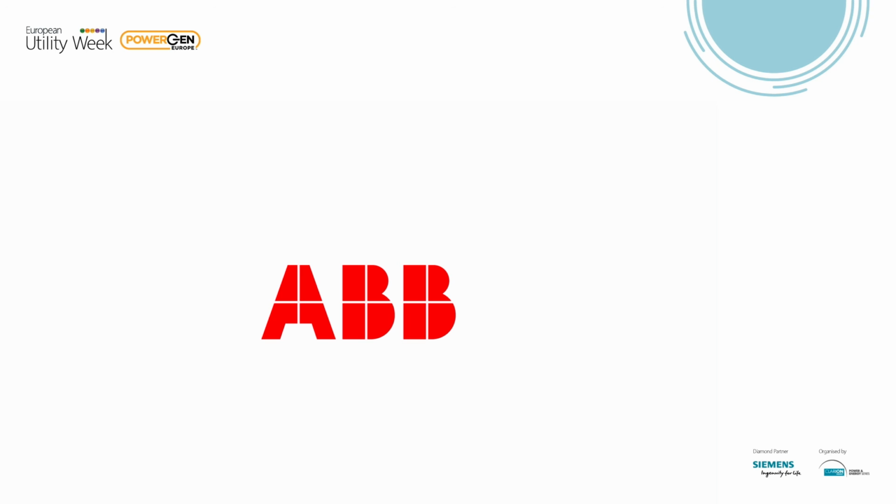We also need something called fast frequency response. The Irish grid did a very clever thing. They divided that into an inertia, which is unfortunately not very defined in time frame, which they call synchronous inertia response, and then they have fast frequency response, which comes afterwards. So you need the synchronous inertia response to help you reduce the rate of change of frequency, and to help you at the nadir, so that you avoid the frequency coming down too low. And then you need a fast frequency response to push the frequency up again, as well as the primary frequency control and secondary frequency control. It's a combination. So the important thing is that we have to build these building blocks together. Synchronous alone is not the solution, and neither is battery alone.